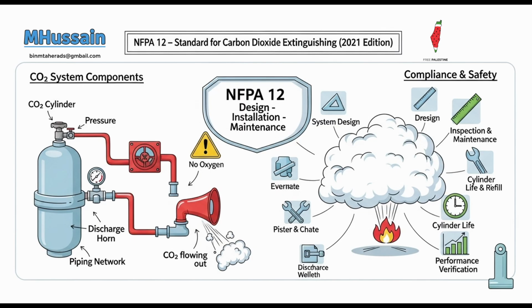So it makes absolute sense that there are extremely stringent restrictions, particularly for what the standard calls normally occupied enclosures. Yes, places where people usually are. Let's unpack this. New total flooding CO2 systems, for instance, are generally not permitted in these spaces. Generally prohibited, that's the rule. What are the very specific exceptions to that rule, and what's the underlying reasoning for each?